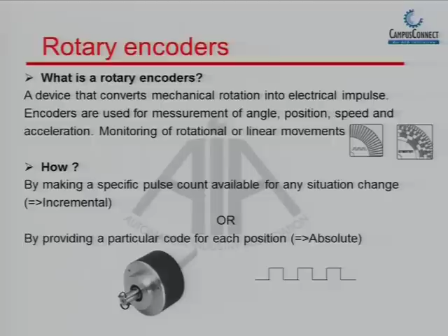Can anybody explain the difference between the two? What is the difference between an incremental encoder and an absolute encoder? Each position is unique in itself, like a gray code encoder, that is the absolute encoder. And for incremental, you need to have a reference beforehand from where it has started. The last position becomes the reference for the next one. Let's say a potentiometer is an absolute encoder because it goes from 0 volt to 5 volt, so each position can uniquely identify itself starting from 0.